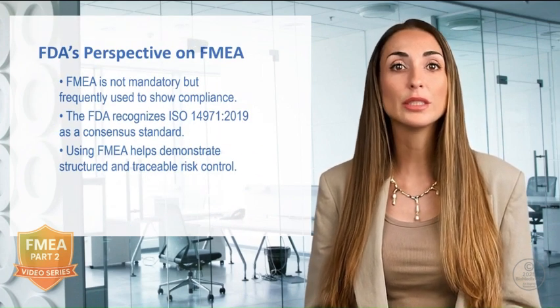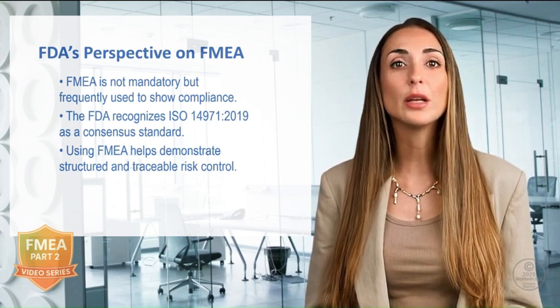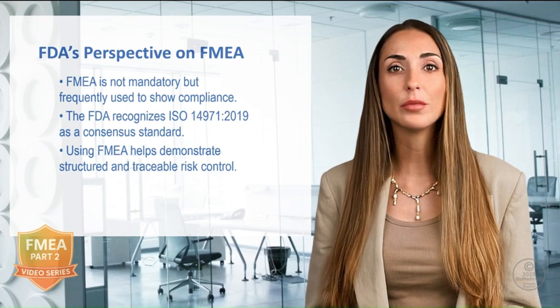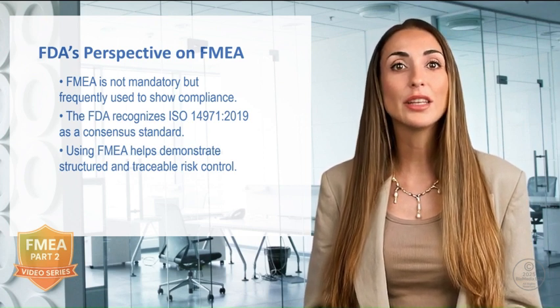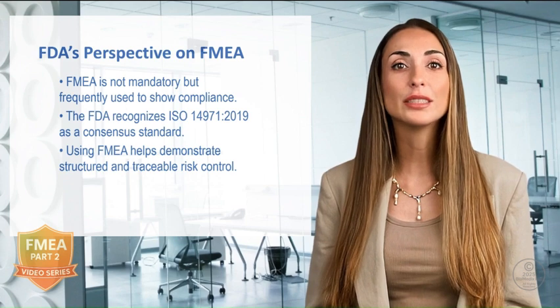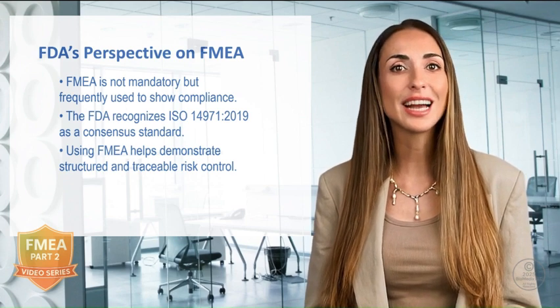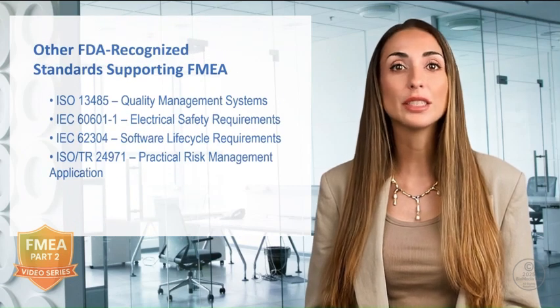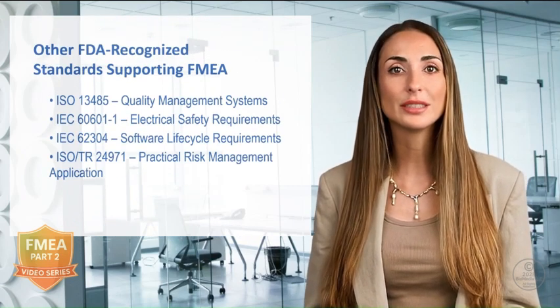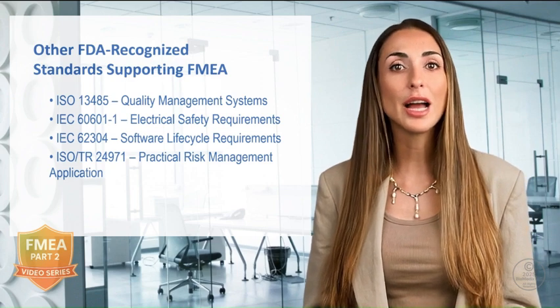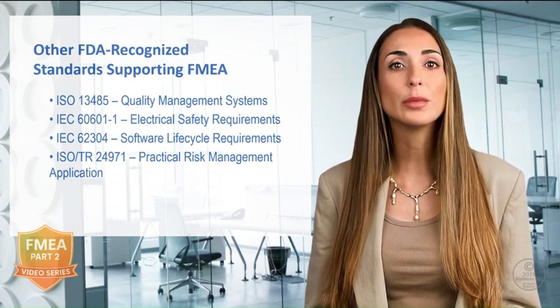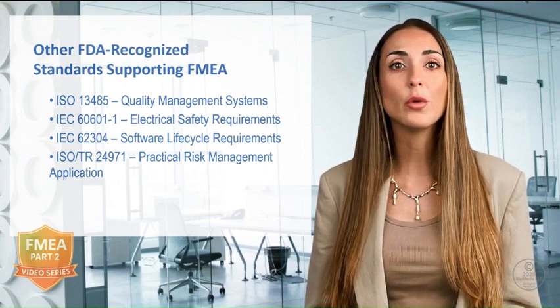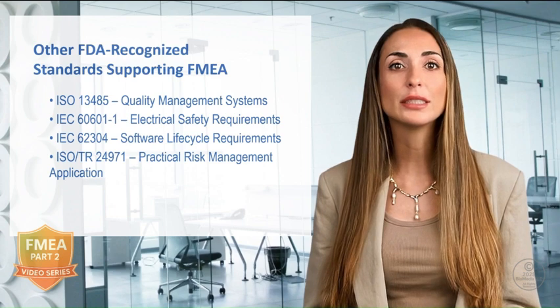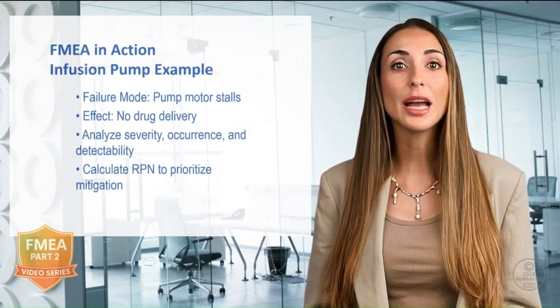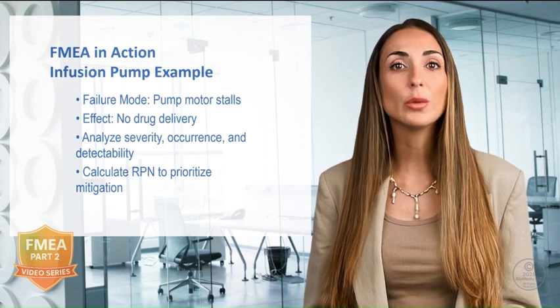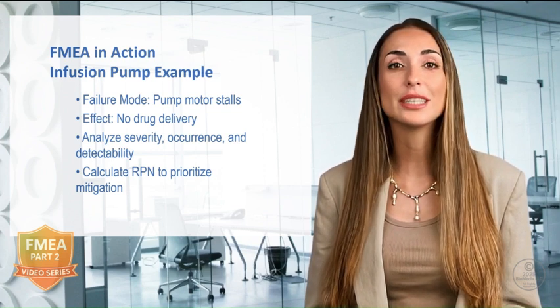From a regulatory standpoint, the FDA does not require FMEA, but it is frequently used to demonstrate that a company has performed thorough and traceable risk analysis. The FDA recognizes ISO 14971:2019 as a consensus standard, and using tools like FMEA under this framework can streamline your path to compliance. Other FDA-recognized standards that often complement FMEA include ISO 13485 for quality systems, IEC 60601-1 for electrical safety, and ISO TR 24971, which provides practical guidance on applying ISO 14971.